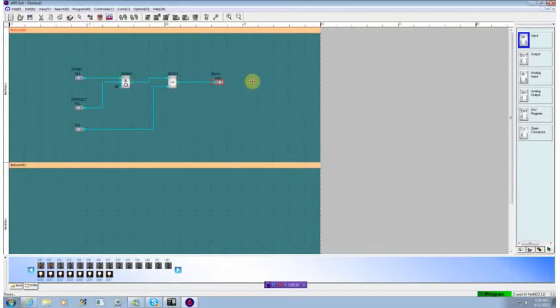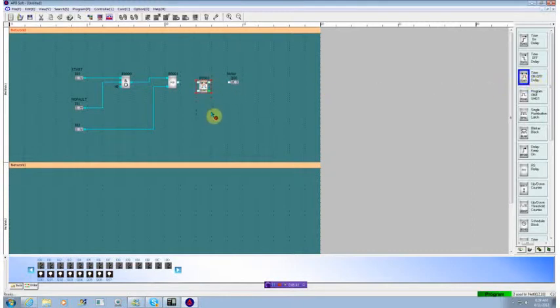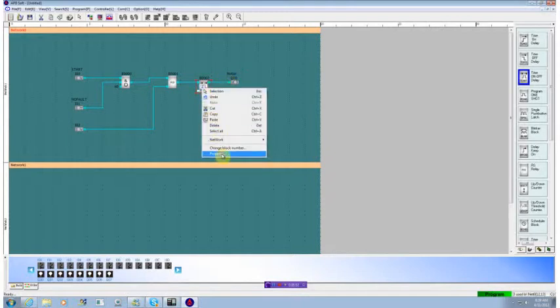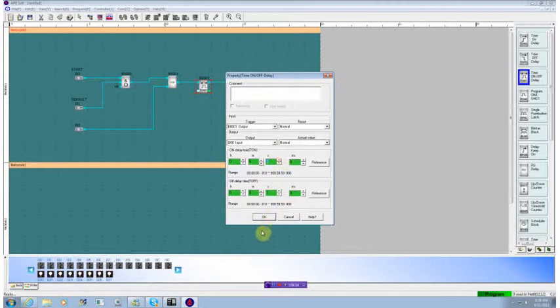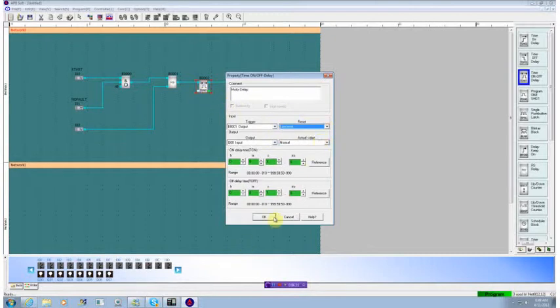Quite often with a motor, you'll find that you want a time on and time off delay. So we'll break this connection. Again, go back to our timer capabilities. We see we have something called time on, time off. We'll move one of those in. The trigger is on the top. The bottom is always reset on these function blocks. So we'll connect this like this. Look at the properties here and see that we can actually set the on delay. So let's set that to three seconds and we'll set the off delay to two seconds. We'll give this a name of motor delay. We'll save that. The one other thing we want to do is we won't be using the reset in this situation. We'll set that to a low level, meaning it never gets activated.